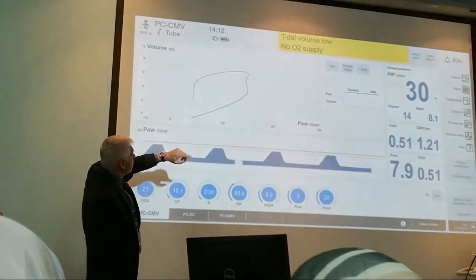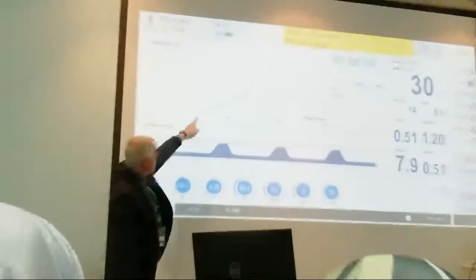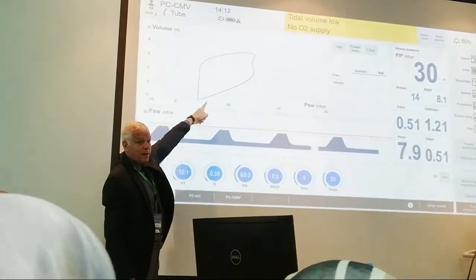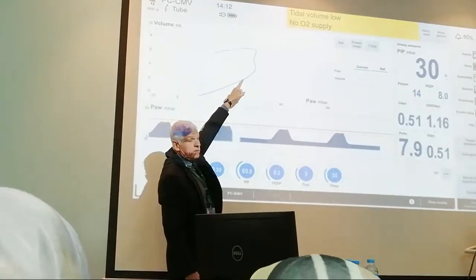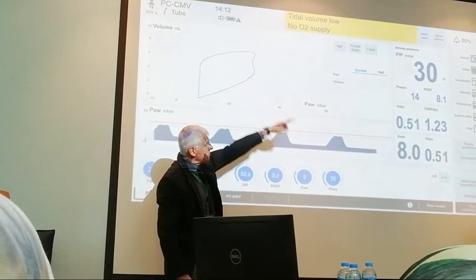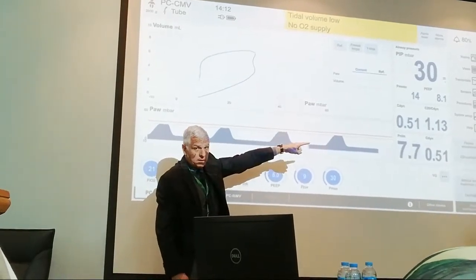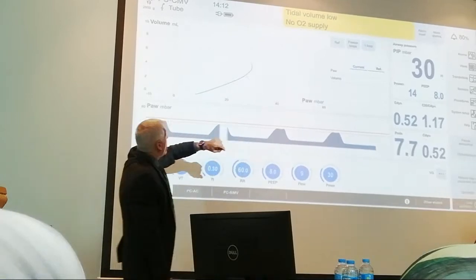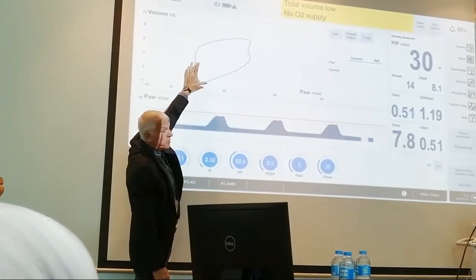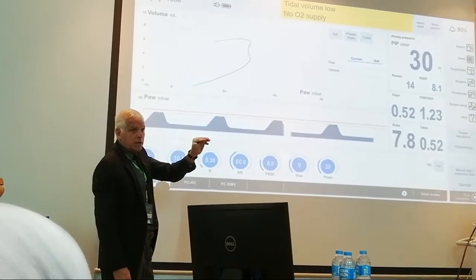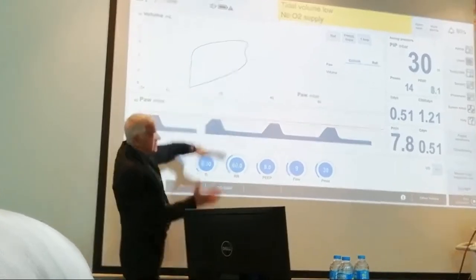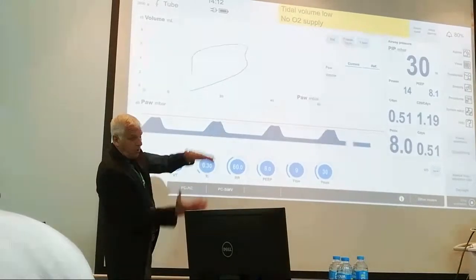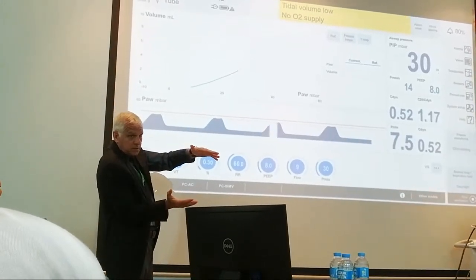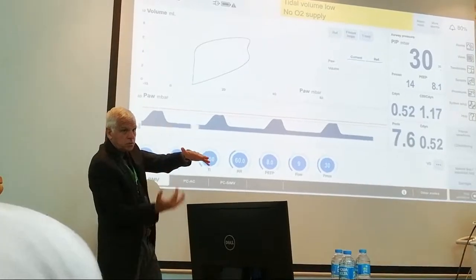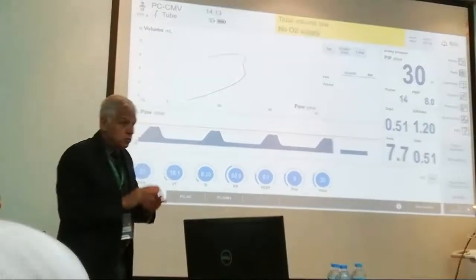In the volume pressure curve, you look at the angle for compliance and the opening pressure, which will tell you exactly what the ideal PEEP is. You will see if there is any leaking or overextension by looking at the shape and also at the C20 over C. You will also look at the separation between the two. If it's too narrow, most likely you have surfactant deficiency. If it's too wide, it depends whether both are significantly bigger or just one. You can see if it's an inspiratory obstruction, an expiratory obstruction, or both. All that information you can get from the volume pressure curve.